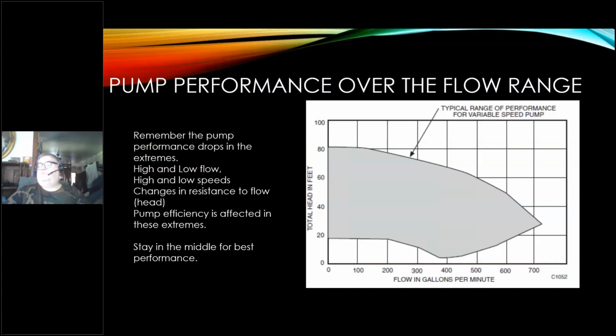Certainly, if you remember your pump curves, they don't improve when you move more water or less water. They are in a sweet spot. They have an ideal condition to operate in, and that's somewhere in the middle. So if you went wide open on this thing, you're going to lose efficiency in the pump. You'll move a lot more water. You'll use a lot more energy, but your pump efficiency will fall off. Stay in the middle for your best performance.